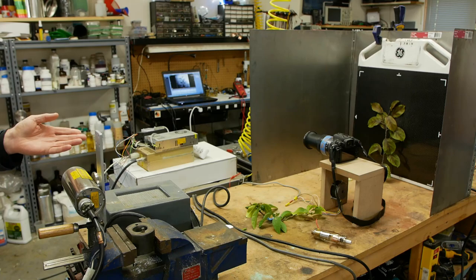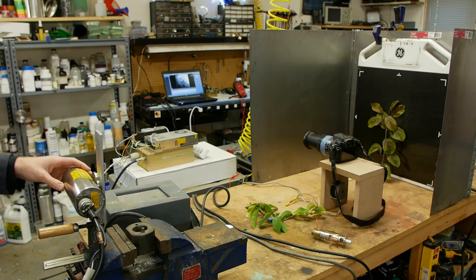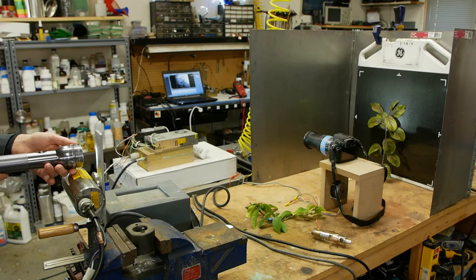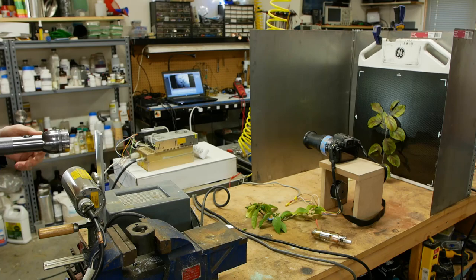The beam size is about the same, the voltage is about the same, and so is the current. So as you can see, we want to stop the primary beam. It helps a lot to think about X-rays like the beam of a flashlight like this, where the intensity of the beam is quite high in the primary beam, of course, and so we want to stop that. And as you can see, I've got a bunch of steel back there to stop the primary beam.